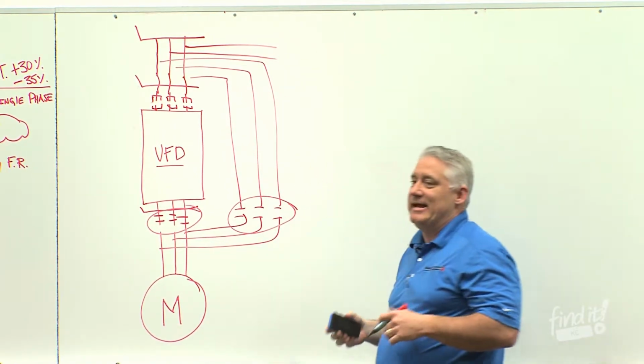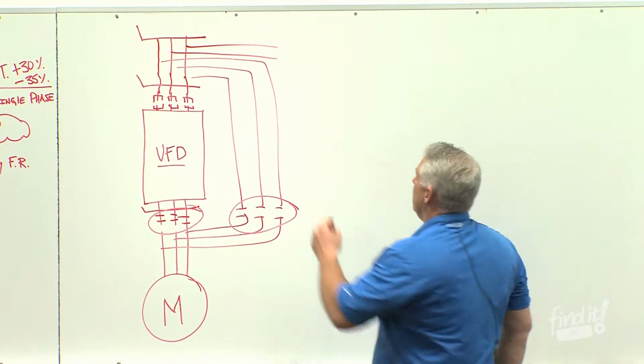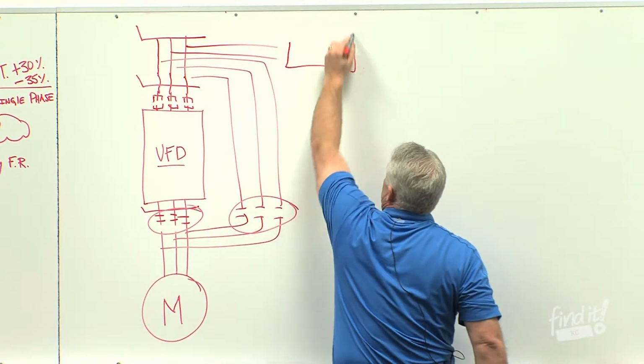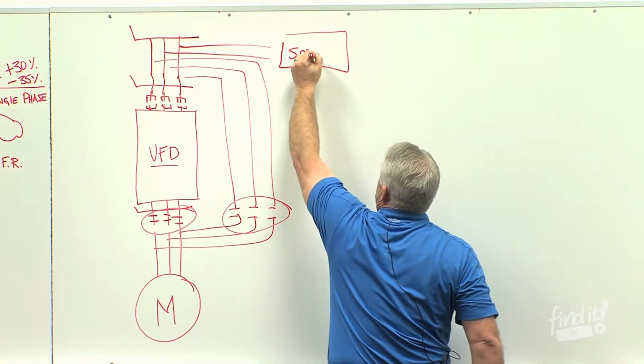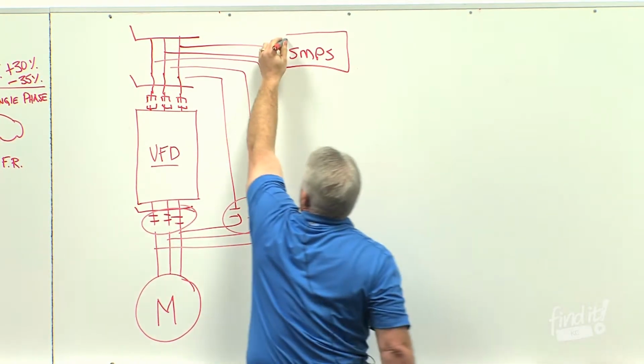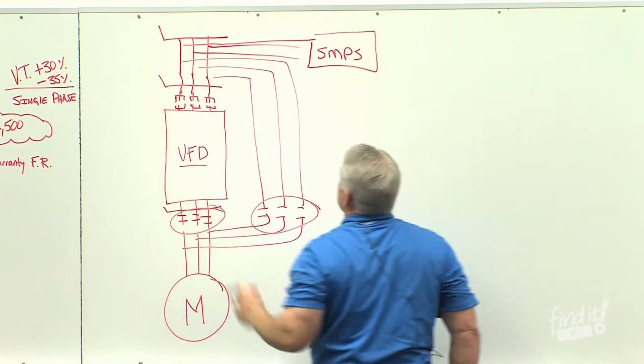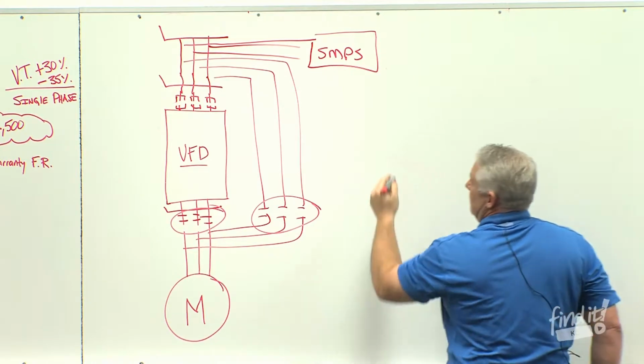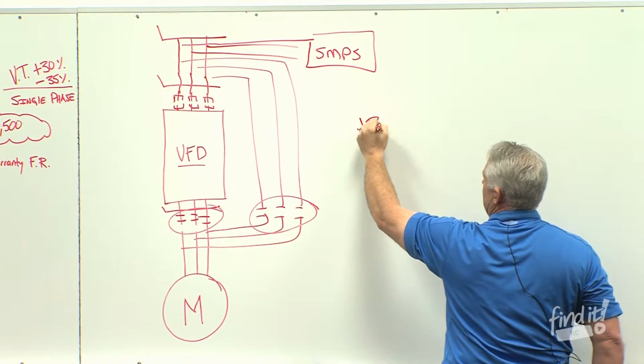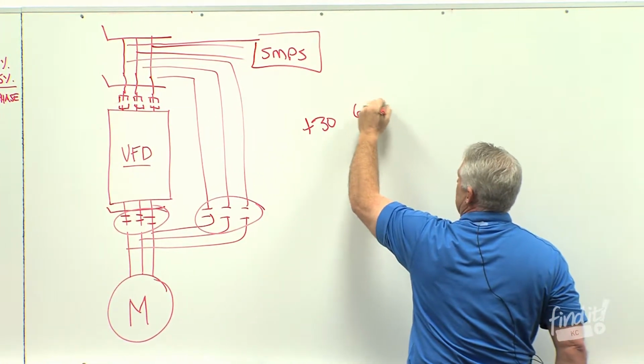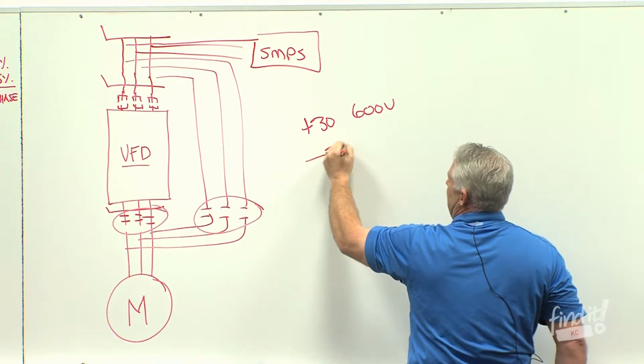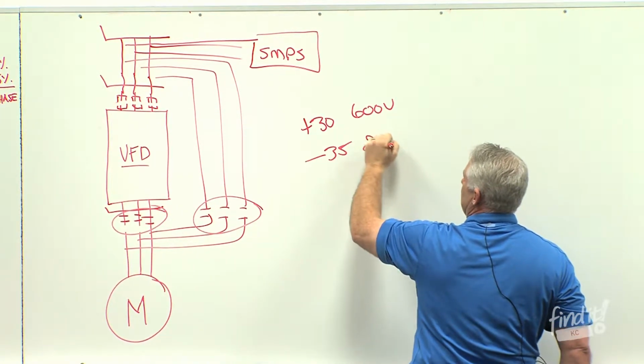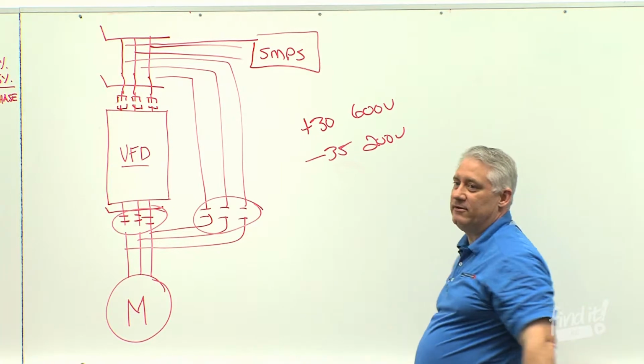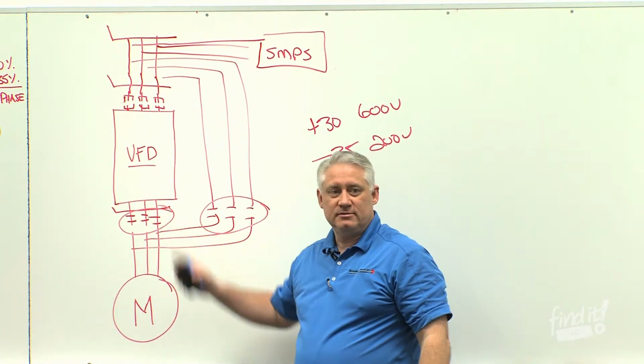Well, we went to a dedicated power supply. We've got rid of the control power transformer. We put a switch mode power supply in here. And we now take power off of all 3 phases. And we now have plus 30 of 600 volts, minus 35 of 200 volts voltage tolerance on our contactors.